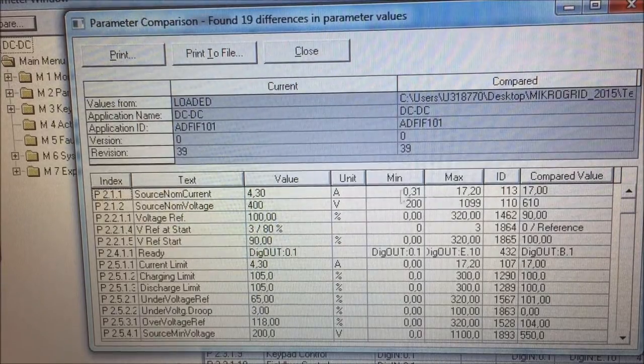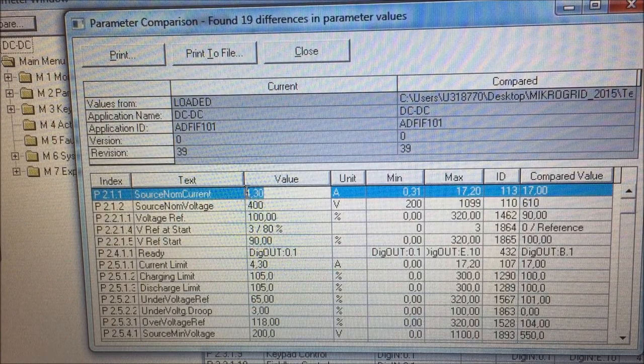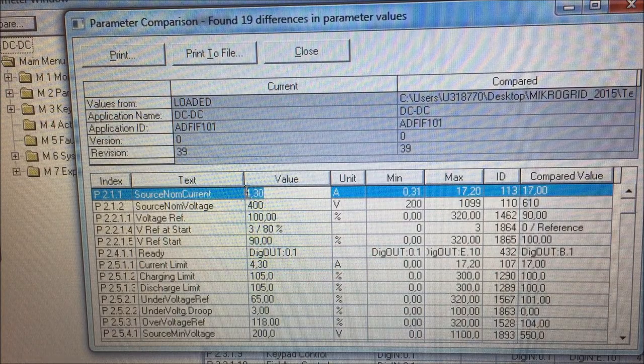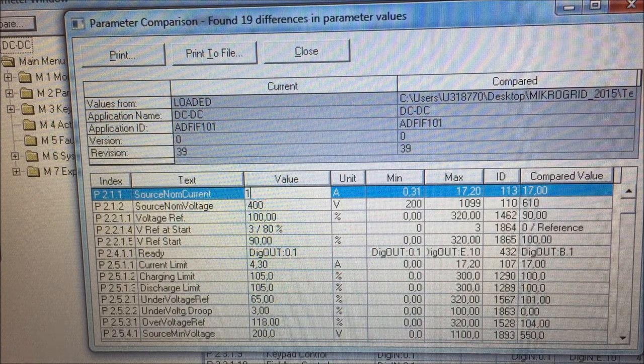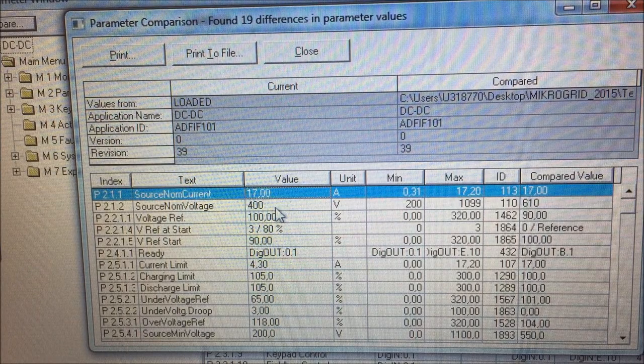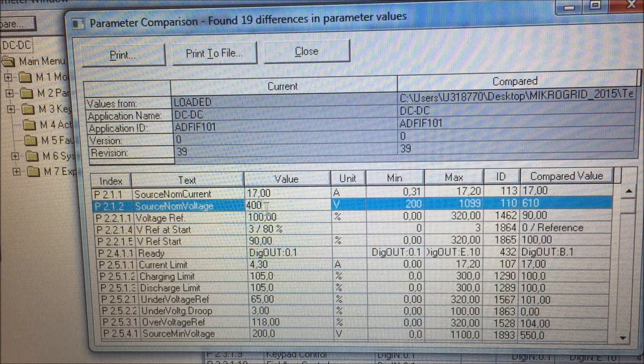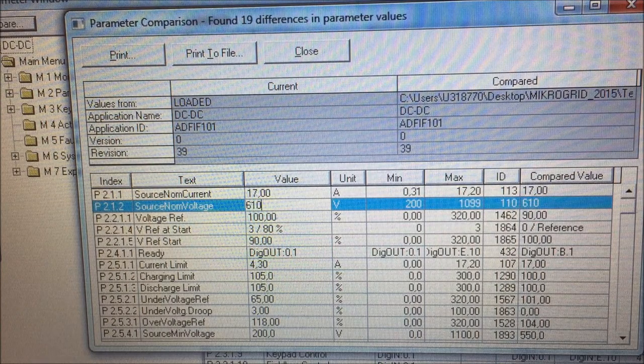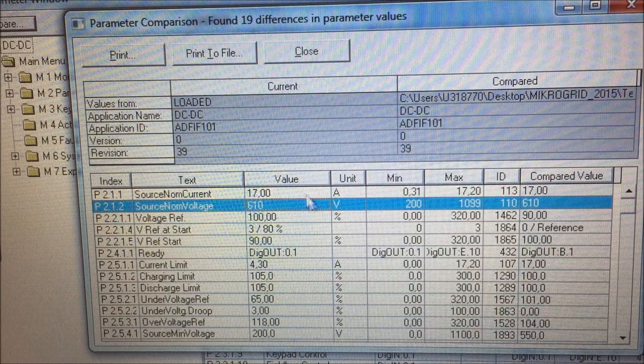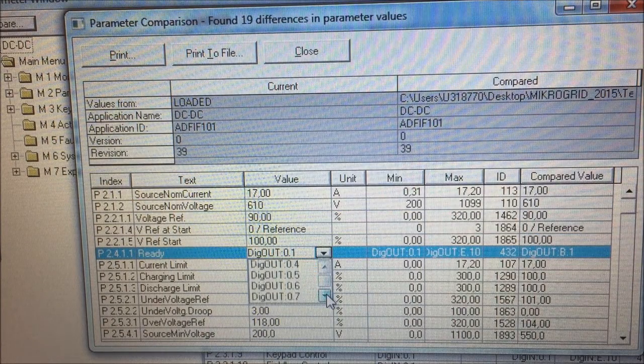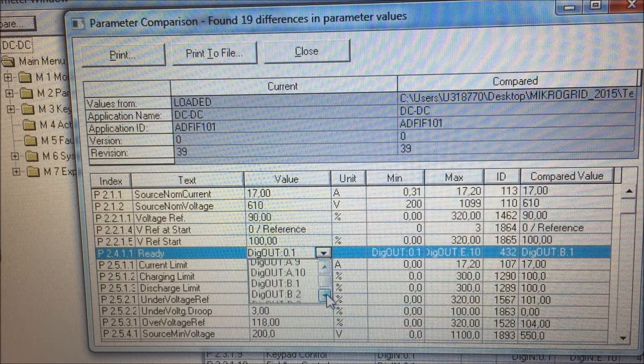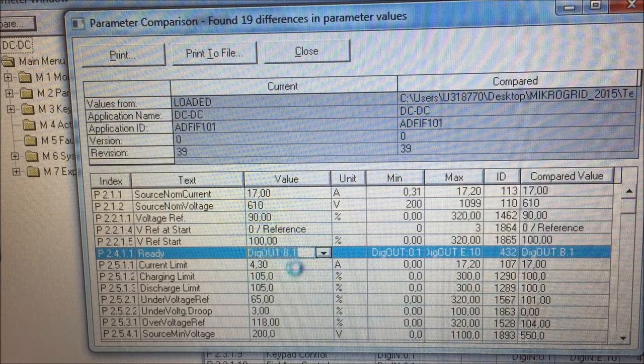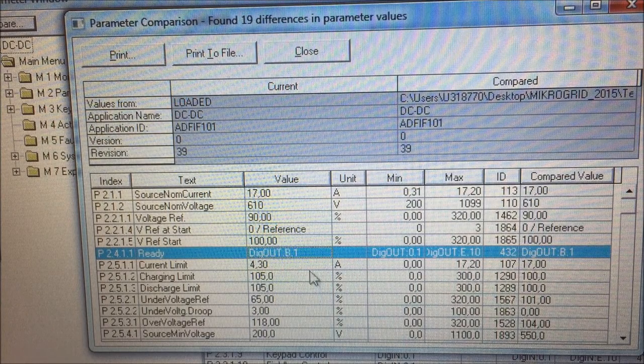The first parameter I change is the source nominal current. That is, source is the battery side and I have quite bigger current capacity here. So I go the full maximum allowed for the DC link here. The source nominal voltage, that is the battery. The nominal of this battery is 610. I have a pre-charge functionality on my first digital output. So I need to set this to B1. That is the first digital output on the B slot.